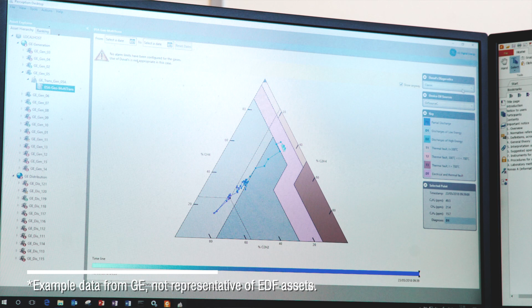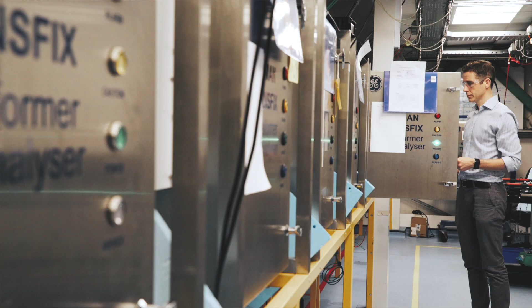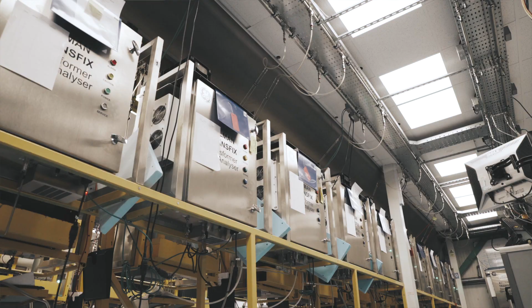We can look at fault gases, moisture and CO2 ratios. I would say the units are extremely good for what they've done for us. On the transformer's life, they're better to have. We've been lucky, we've caught, I think, in the region of about 5 or 6 before it's gone to a catastrophic failure. You can weigh up what's the cost of, you know, a transfix against losing a transformer.